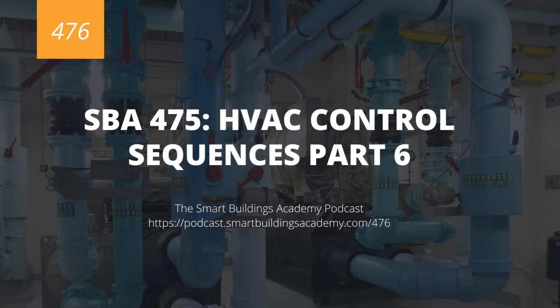Now, water-cooled chillers work by discharging heat from refrigerant into condenser water. The condenser water is then pumped out to cooling towers, and these cooling towers have fans and spray nozzles. They essentially utilize the effect of drawing air across the surface of the water, or using the spray nozzles to create a mist and then drawing the water through the mist.